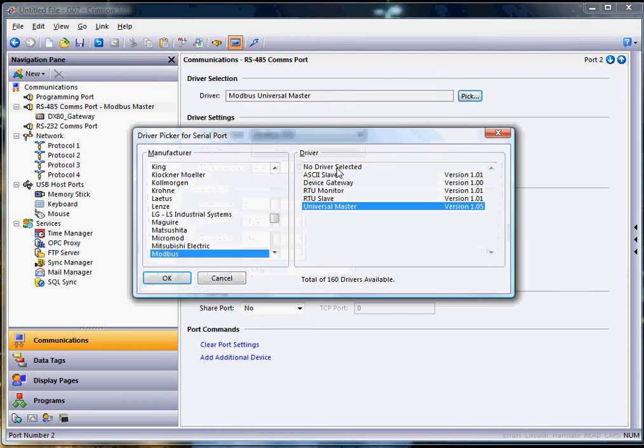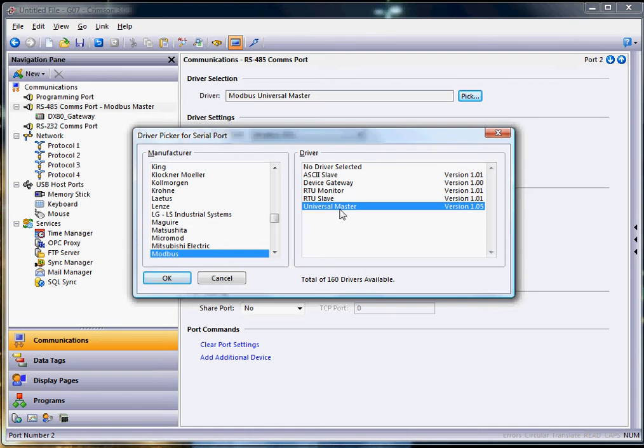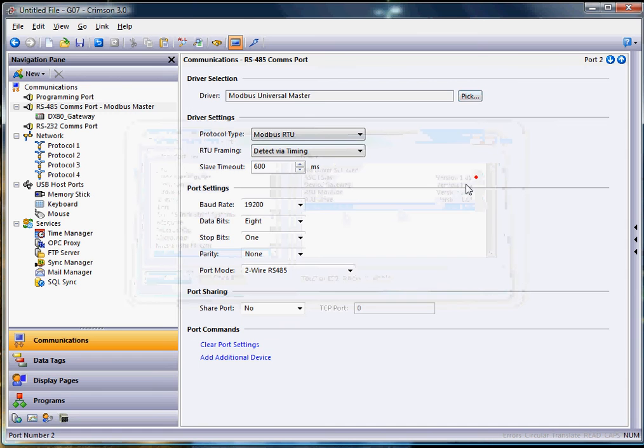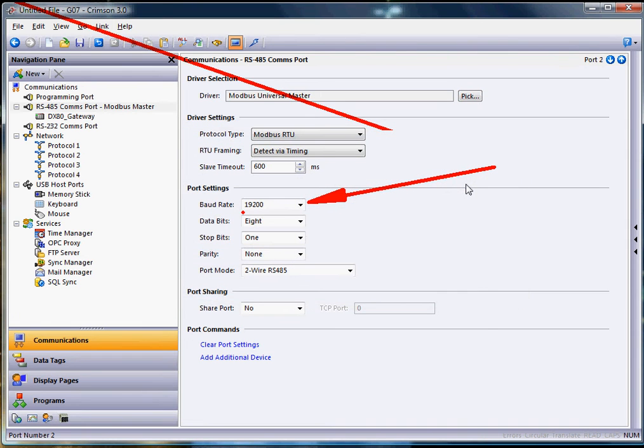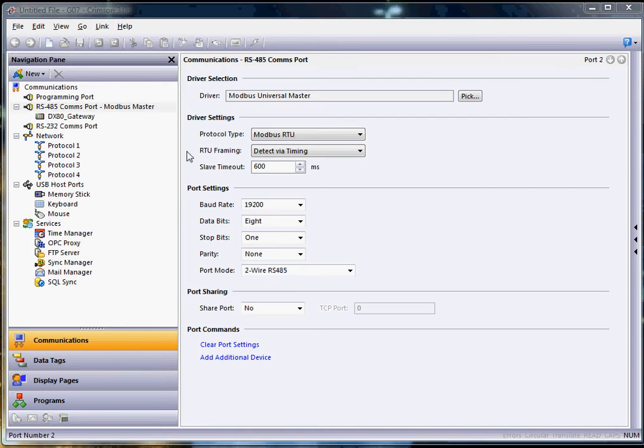You can always hit the pick button right here, select the Modbus category for the manufacturer, and choose Universal Master because I'm using that to talk directly to the wireless gateway. Keep in mind that the gateway for Banner, as a default, is 19200 for the baud rate. All the rest of the settings are set the same.